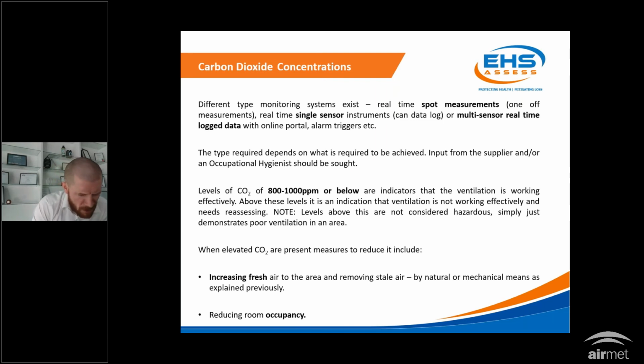That's been referenced in a lot of material, particularly out of the US. The CDC in the US, and also Harvard, have basically stated that between 800 and 1,000 parts per million is a good point to aim for. We also need to remember these levels are very low. They're not health effect levels, as in no one's going to have health effects at levels greater than 1,000 parts per million. These are indoor air quality measures, basically comfort measures. Therefore, they're pretty low, and you need pretty good ventilation in place to achieve those sort of levels.